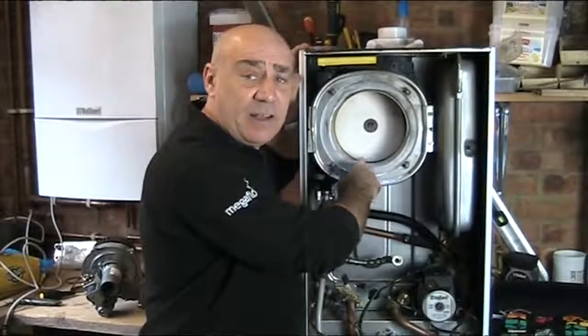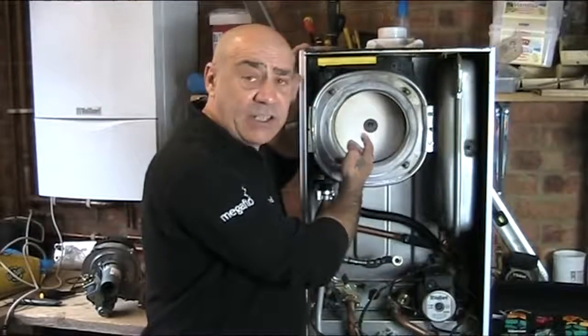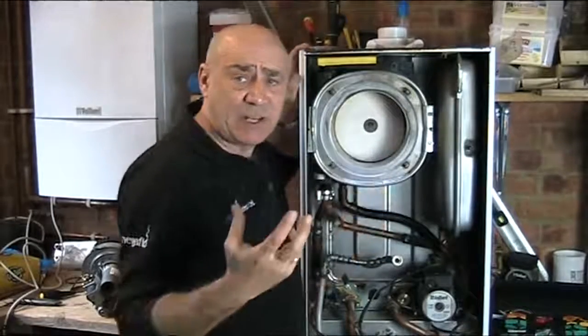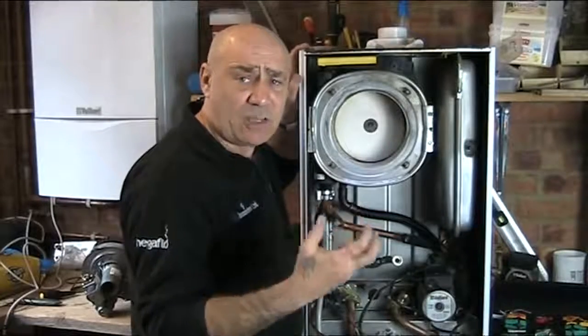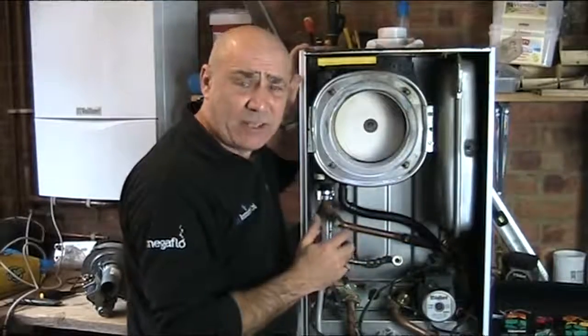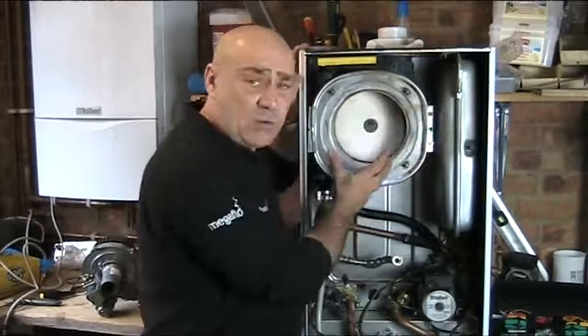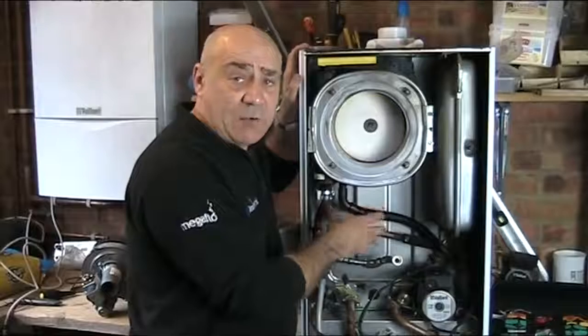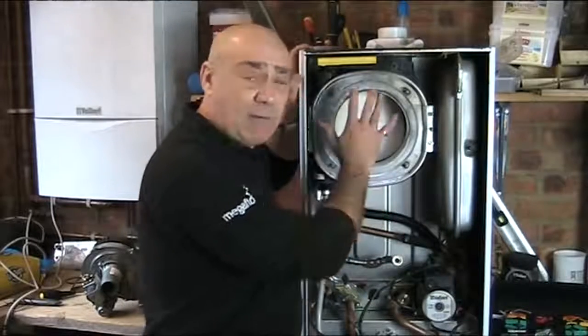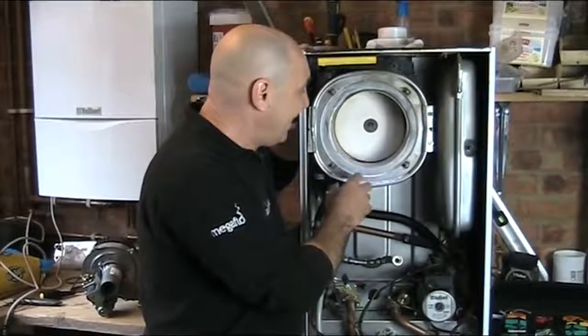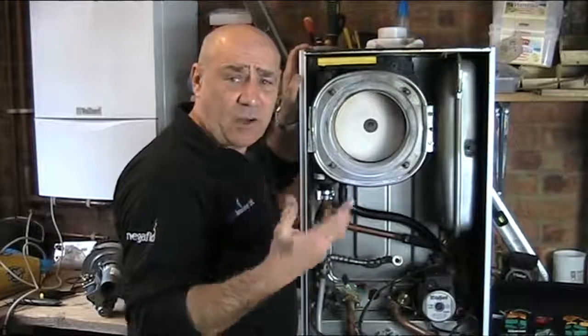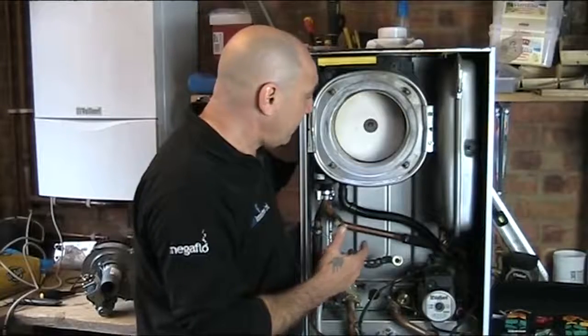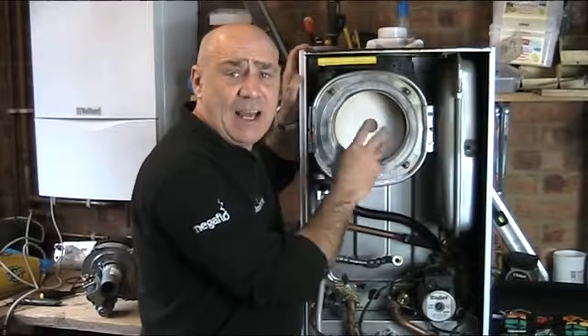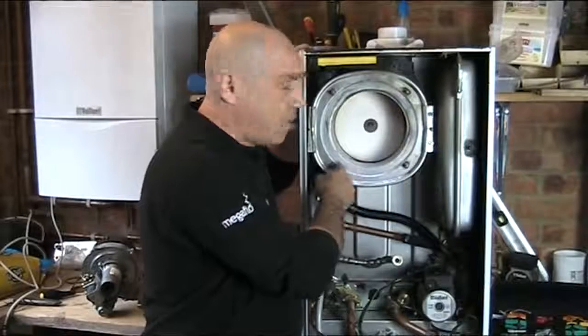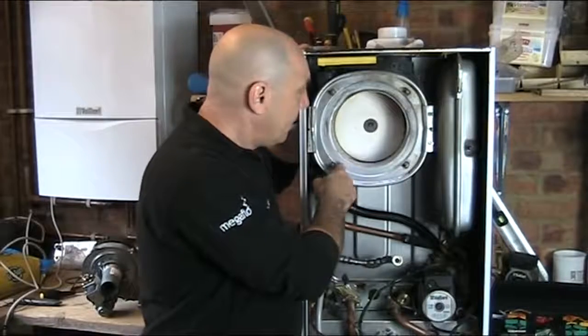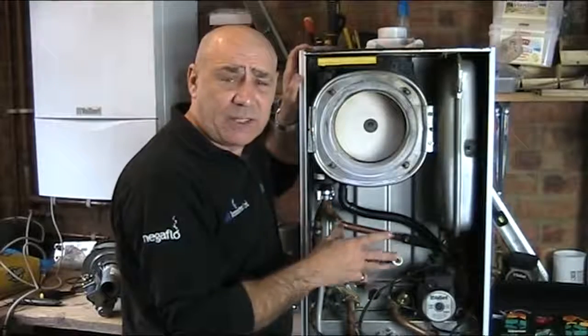So this is one area, again, biannually we will clean out the heat exchanger, make sure all the fins are nice and clear so it doesn't affect the combustion, and we can transfer the heat nice and quickly into the water that's zipping around inside of that heat exchanger. Once we've done all that, we will then reassemble the gas assembly and put it all back together again, and that will be the heat exchanger and burner done. The other thing, again, which is quite critical on this type of boiler, is ensuring that the seal is intact and it's actually made a full seal all the way around the heat exchanger fascia. Once that's done, that's most of the gas side of it completed.